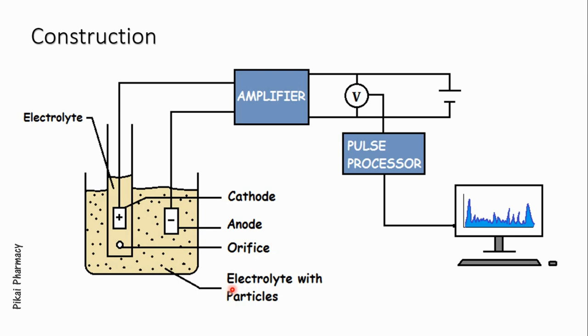The outer container contains electrolytic solution plus suspended particles. There is a hole, or better to say an orifice, at the bottom of this glass tube, and there are electrodes dipped in both solutions.